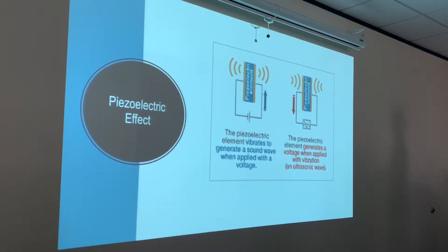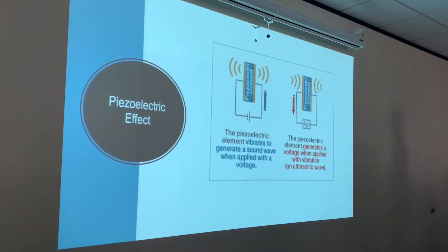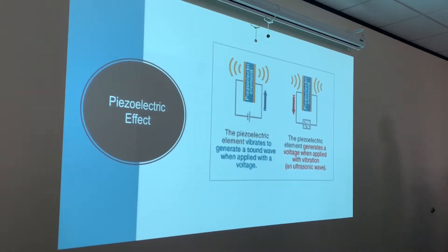Our wire coming in causes the PZT to vibrate and generate sound waves. During reception, that is the piezoelectric effect; during transmission, that is the reverse piezoelectric effect. The piezoelectric element generates a voltage when vibration is applied to it, and an ultrasonic wave is produced when voltage is applied to it.